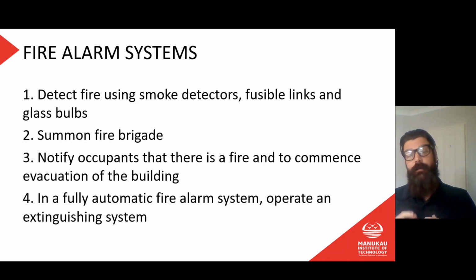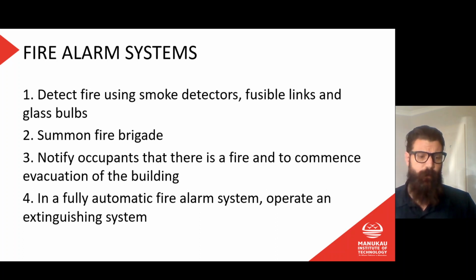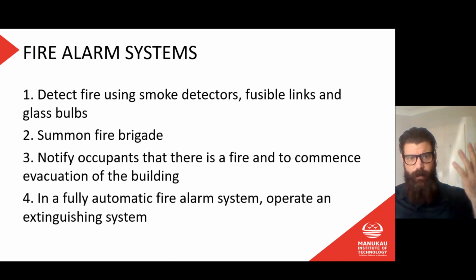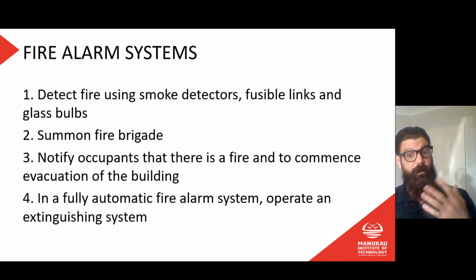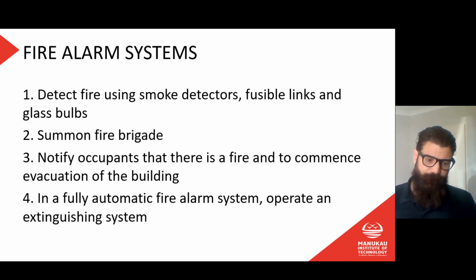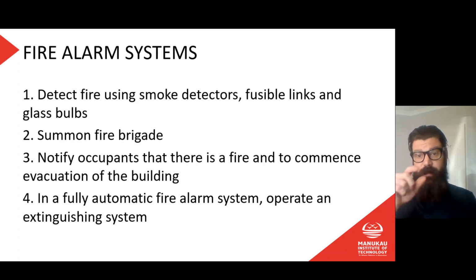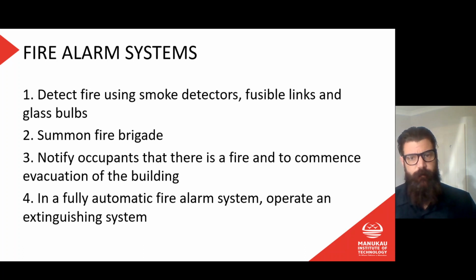Okay, so a few points there. Generally you have heat detectors and smoke detectors. Again, they'll be for different purposes. A smoke detector will detect smoke. A heat detector will detect heat. Usually, for example, you won't have smoke detectors in a kitchen because the steam or a bit of smoke from burnt toast or something can set off a smoke detector, and you don't want the fire alarm to go off every time somebody burns toast. So generally there you'll have a heat detector, which is the fusible link type. Once it gets to a certain temperature, the little bit of metal melts, and that's what sends the signal to the control panel.